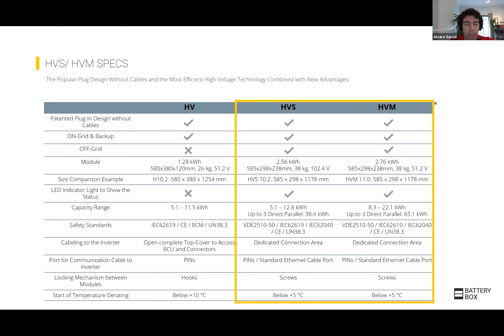In terms of specs, a couple of very important things to take into consideration: remember the voltage and the current you can go per tower. The HVS accepts up to 25 amps of current, the HVM 50 amps. You need to look at the same time at the maximum current that goes through the inverter — I'll show you afterwards an example of how to calculate the power of the systems. A very important factor is that derating starts at 5 degrees, actually improved now to 0 degrees, but at that temperature the charging power of the batteries needs to be decreased. This is because lithium-ion batteries at low temperature need to be protected, so the current through them needs to be reduced to maximize the life of the product.